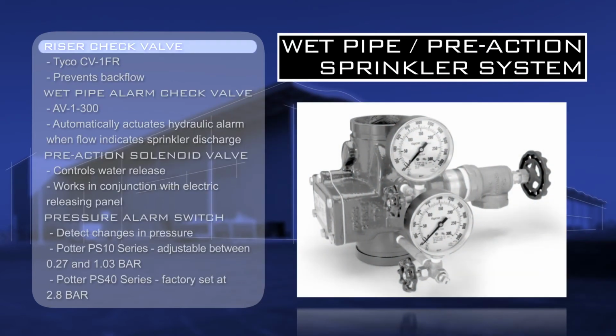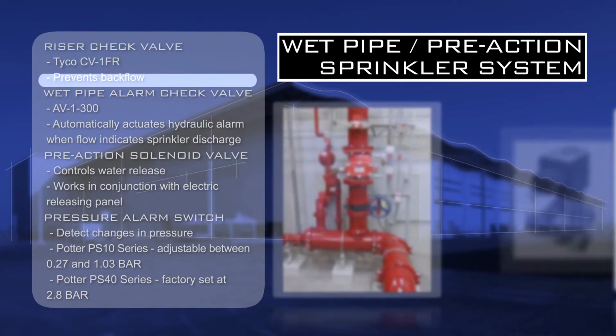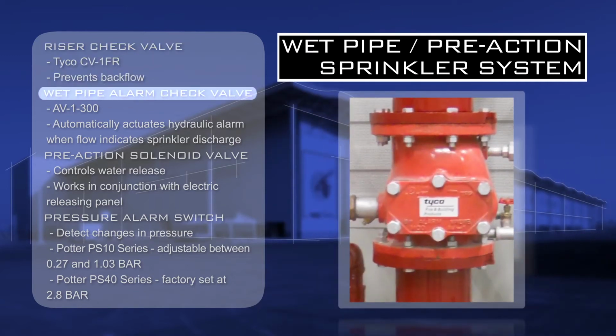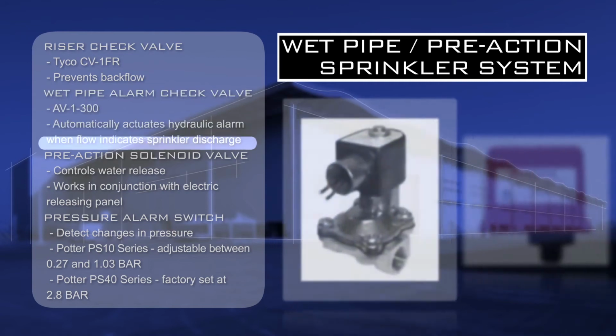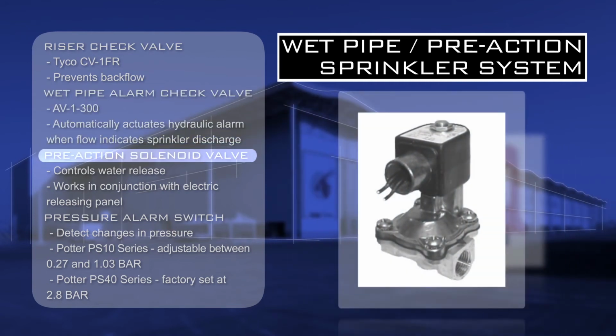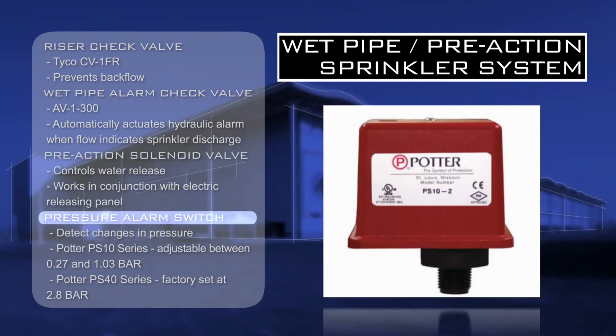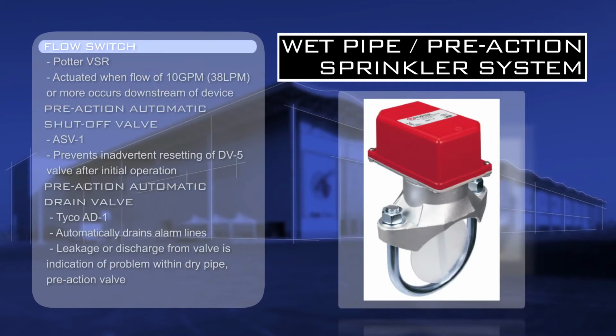The riser check valve prevents backflow. The wet pipe alarm check valve automatically activates the hydraulic alarm when the flow indicates sprinkler discharge. The pre-action solenoid valve controls water release and works in conjunction with the electric releasing panel. The pressure alarm switch detects changes in pressure. The Potter PS10 series is adjustable between 0.27 and 1.03 bar, while the Potter PS40 series is factory set at 2.8 bar. The flow switch is activated when a flow of 10 gallons per minute or more occurs downstream of the device.